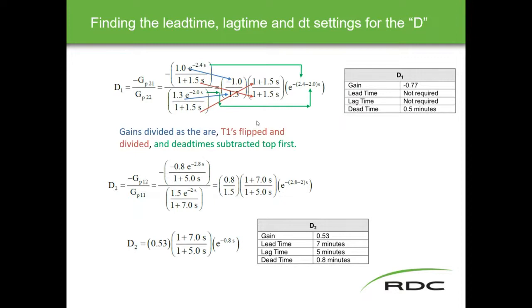The process for finding lead time, lag time, and dead time — hopefully less messy this time with color-coded arrows. Gains are divided: the upper gain divided by the lower gain, so top over bottom. The T1 times get flipped — top goes to bottom and bottom goes to top. Not a great example because of the exact same number here, but in any other case they would be obviously flipped. Dead times are subtracted top first: 2.4 minus 2.